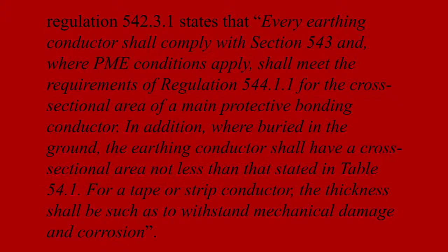It's the second part of that sentence which says, and where PME conditions apply, we shall meet the requirements of regulation 544, which is protective bonding. So if we've got a PME system, we need to consider it even when we're looking at that earthing conductor, that incoming earth. The sizing still has to be related to the requirements for bonding. So that will be based on the incoming neutral, and we won't be able to purely use the adiabatic equation to size that. So, today's question of the week, the correct answer would have been D.